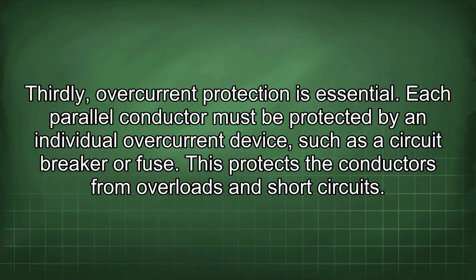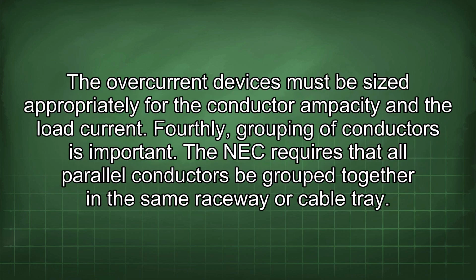Thirdly, overcurrent protection is essential. Each parallel conductor must be protected by an individual overcurrent device, such as a circuit breaker or fuse. This protects the conductors from overloads and short circuits. The overcurrent devices must be sized appropriately for the conductor ampacity and the load current.